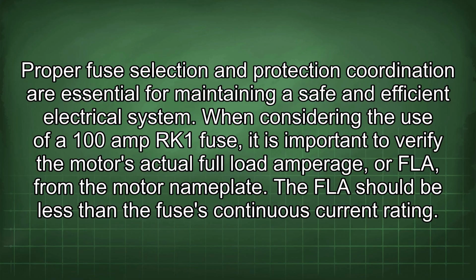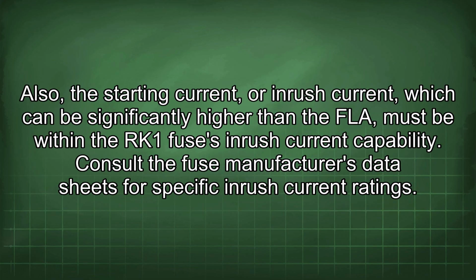When considering the use of a 100 amp RK1 fuse, it is important to verify the motor's actual full load amperage, or FLA, from the motor nameplate. The FLA should be less than the fuse's continuous current rating. Also, the starting current or inrush current, which can be significantly higher than the FLA, must be within the RK1 fuse's inrush current capability. Consult the fuse manufacturer's data sheets for specific inrush current ratings.